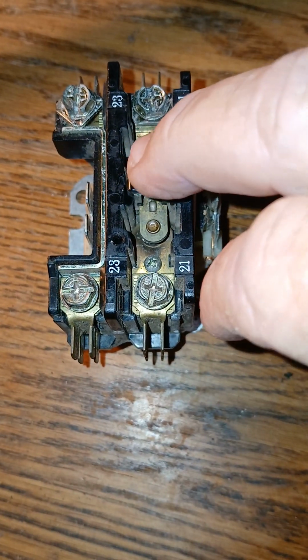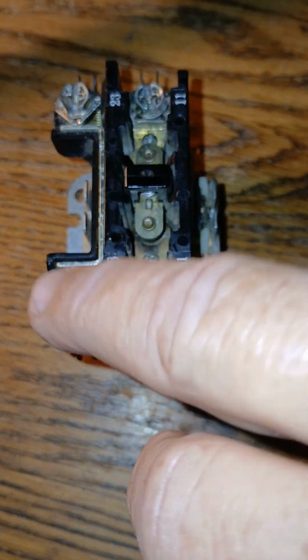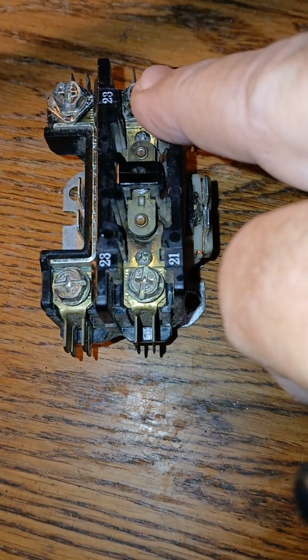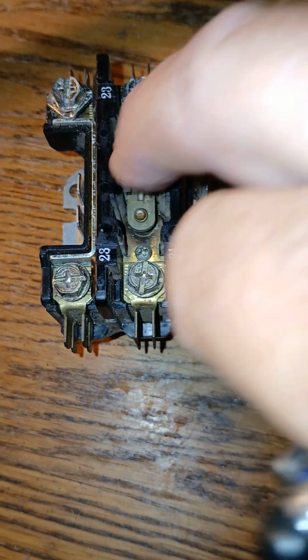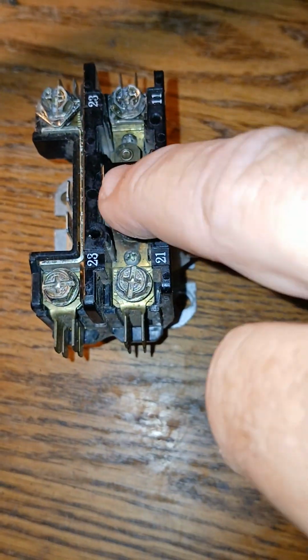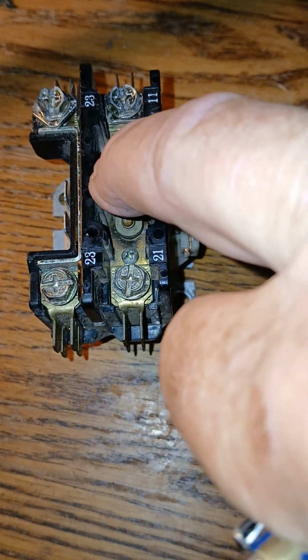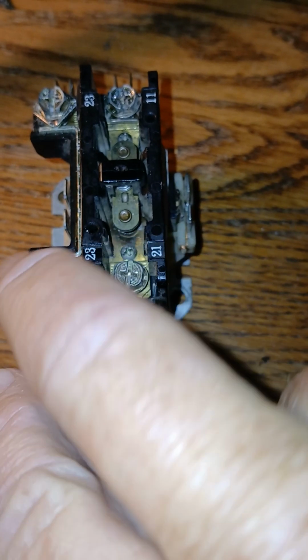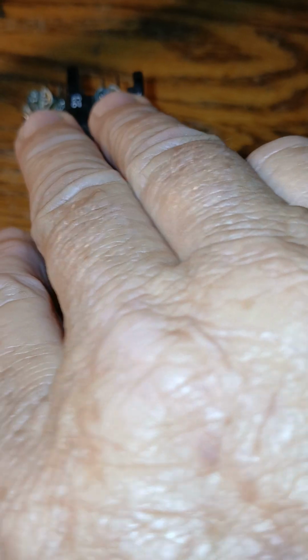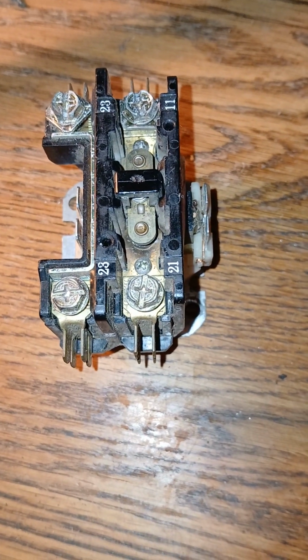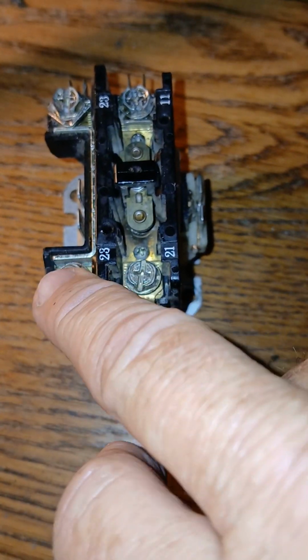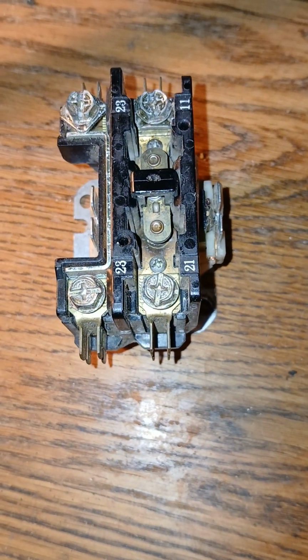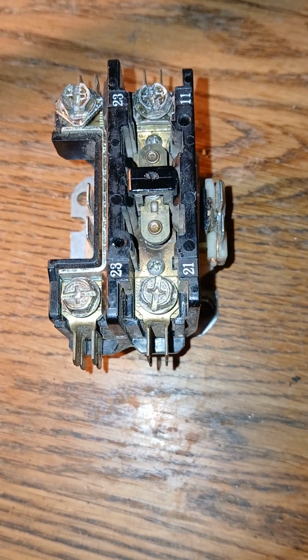So basically, this is how it's energized. Low voltage energizes high voltage. This would be high voltage after energized. This would be low voltage from here and here to pull this in with the coil. Once the low voltage pulls this in, the high voltage jumps from here to here to here to here. So you have 120, 120, 120. Now this is pulled in, so you would have 120, 120 here if you put your voltmeter on it. Again, once it's satisfied, it comes up. Then you would have no voltage here. You would still have 120 here, 120 here. And this is simply how an HVAC contactor works.